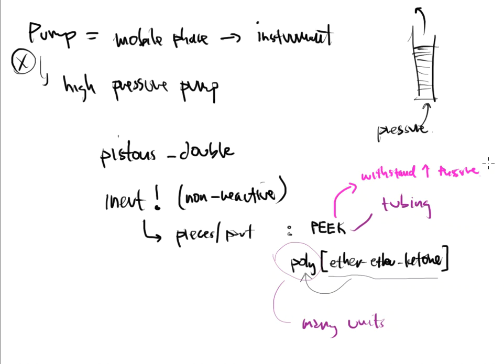So good things about PEEK: number one, it's chemical resistant and very inert, it's not going to be reactive. And number two, it can withstand very high pressure. So you're going to see this PEEK tubing not just in IC, but also in HPLC, and really in any type of LC method that is out there. Anything dealing with liquid mobile phases traditionally go the route of PEEK tubing because it's done such a good job doing what it's supposed to do with very little problems that I need to take care of as a user.